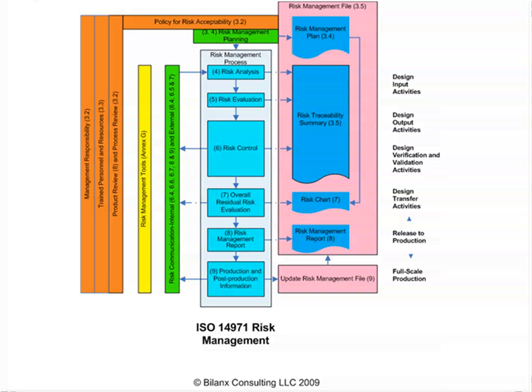Now, the risk management file is really a virtual file in many cases. We don't have necessarily a file drawer that contains a file folder that is titled risk management file that contains a lot of paper documents in it, although some companies do that, and that's one way of doing it. Another way might be putting a file folder in place which says risk management file, and then inside that document we would have an index which tells us all the documents that are supposed to be in that risk management file and then where they're located. And those could be in other file folders that could be in other locations. For instance, if our manufacturing facility is located in a different country even, there might be a document in there from the risk management activities that were conducted in development of the manufacturing process.